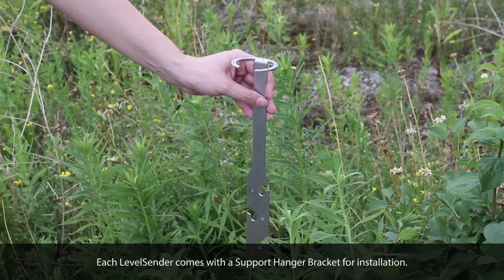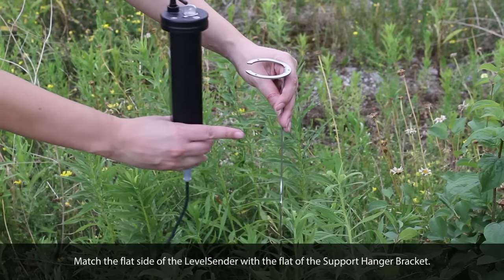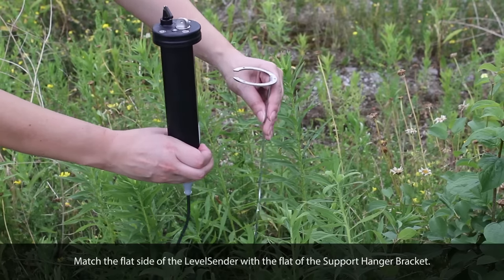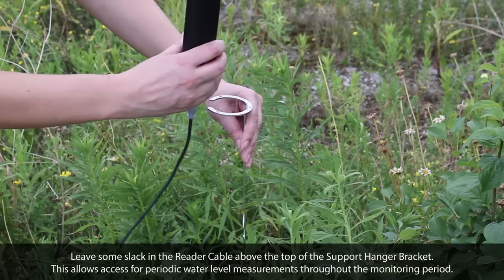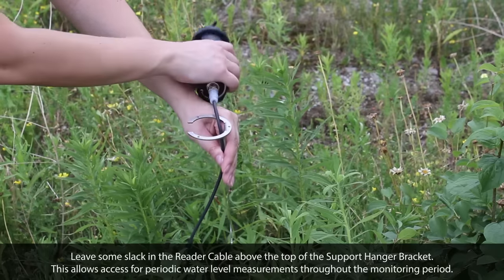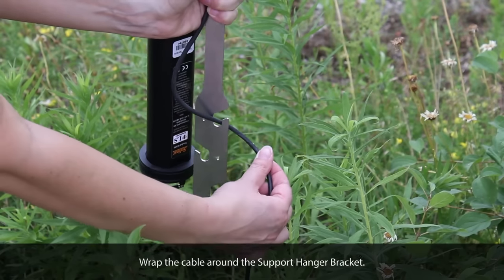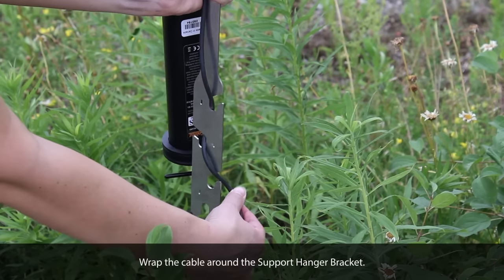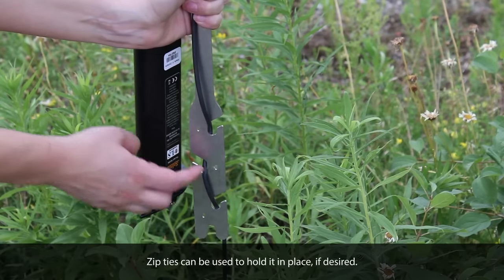Each LevelSender comes with a support hanger bracket for installation. Match the flat side of the LevelSender with the flat side of the support hanger bracket. Leave some slack in the reader cable above the top of the support hanger bracket — this allows access for periodic water level measurements throughout the monitoring period. Wrap the cable around the support hanger bracket. Zip ties can be used to hold it in place if desired.